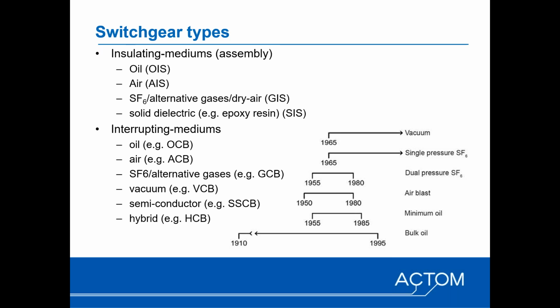So in terms of insulating mediums, not that this is necessarily exhaustive, but the most common types are oil, often referred to as oil insulated switchgear, AIS or air insulated switchgear. Then you've got groups of different gases. Predominantly in the market is still SF6, sulfur hexafluoride. There are also now alternative gases and gas mixtures which are being developed by certain manufacturers as an attempt to reduce or provide alternatives to the SF6 gas due to the global warming potential of SF6.